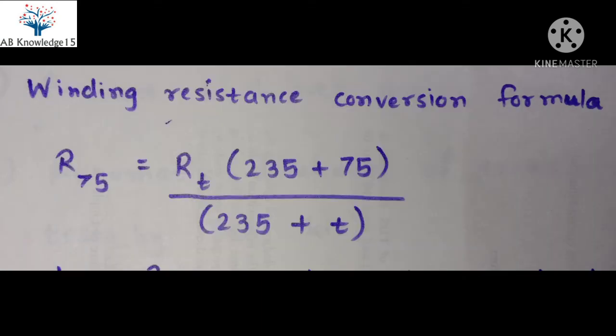This is the winding resistance conversion formula, where we have to convert the winding resistance to the standard temperature of 75 degrees. Here R75 is the winding resistance at the standard temperature of 75 degrees, which we have to find from this equation. RT is equal to the winding resistance at the measured temperature. 235 is the correction factor for copper. T is the winding temperature, which is the average temperature of the insulating oil.